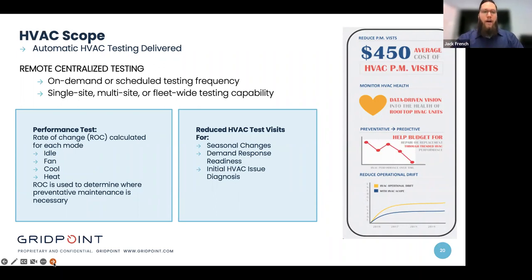So we can do this by running tests remotely and determining which units are responding the way we would expect them to, and which units didn't pass the test or didn't respond the way we expect them to. That way we have an idea of where we may have comfort concerns before they even happen, before the season actually changes. So this can be on demand or scheduled, which really makes this a powerful tool because you can do your PMs and then you can run scope again and see, hey, do I have a lower failure rate now? Because I just did PMs, so I should, right?